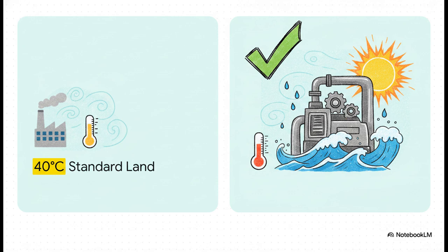You always, and I mean always, choose the 45-degree unit. Offshore ambient conditions are absolutely not just a footnote on a spec sheet, they are a massive design driver. Heat, humidity, and salt spray degrade insulation and contacts far faster than any onshore installation. Your actual switchboard room temperature, sitting right under that tropical sun with an intense machinery heat load, is going to run so much hotter than any temperate climate default. And that is exactly why marine specs carry much harsher derating than industrial land equivalents.